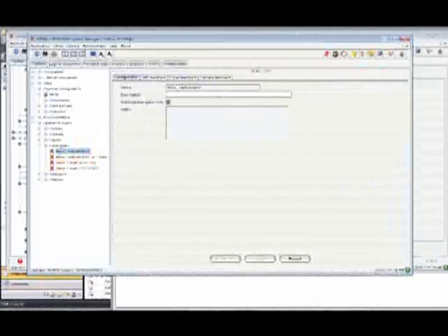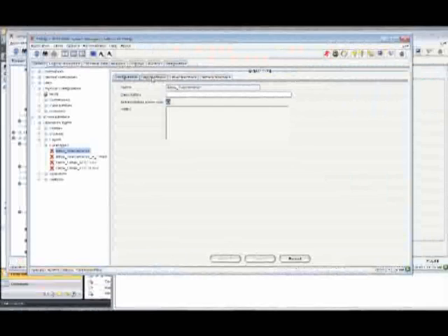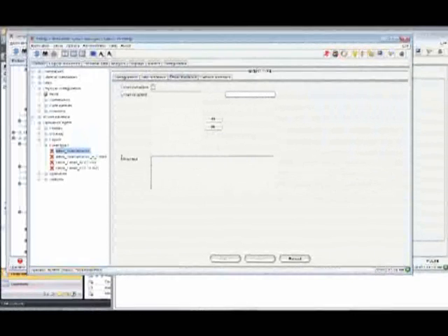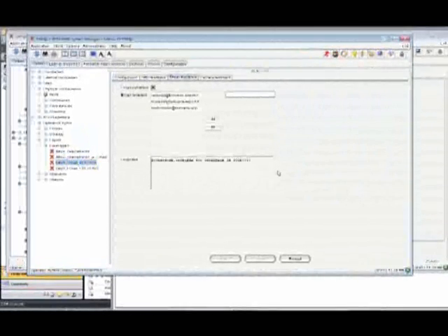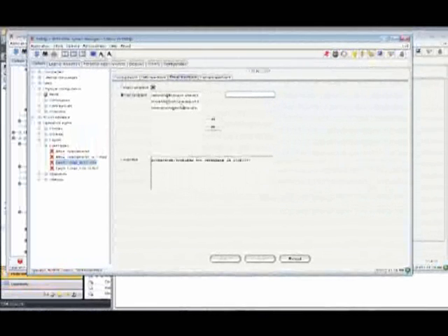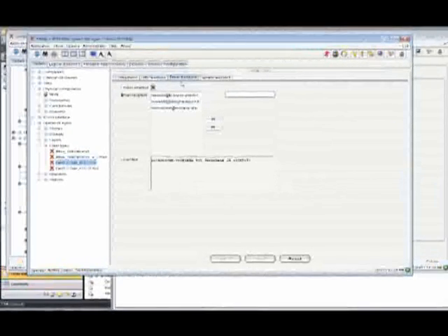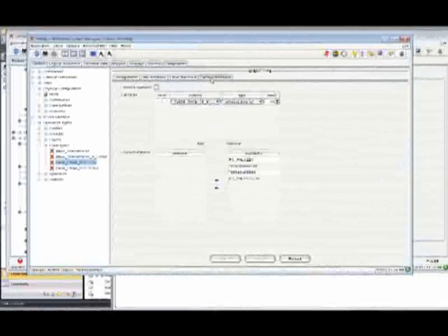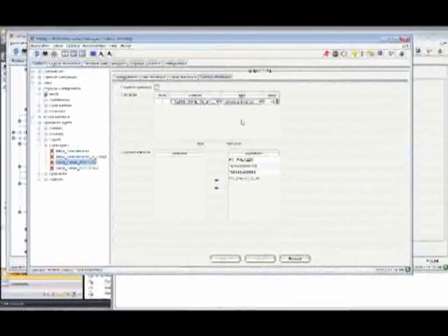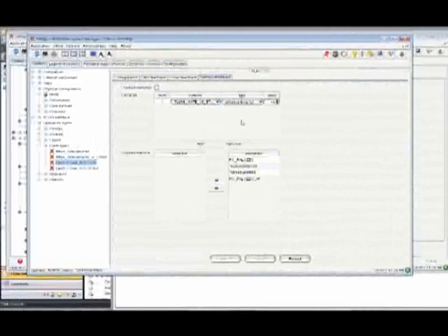So here you see when you define an event and you give a name, you have the possibility to send an SMS to a number of phones, to send emails. Here they are not using that. In this case, we have the case of the event, and in case this event is triggered, we have 3 emails with the subject sent to these 3 addresses. And in addition, the possibility to pop up a camera view on the screen of some specific workstations.